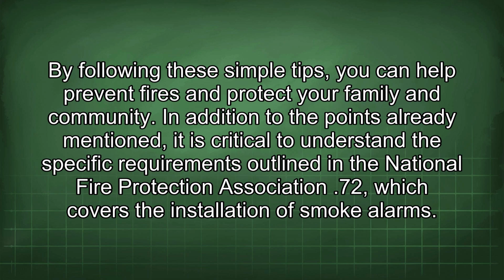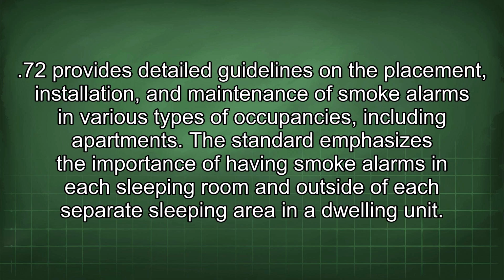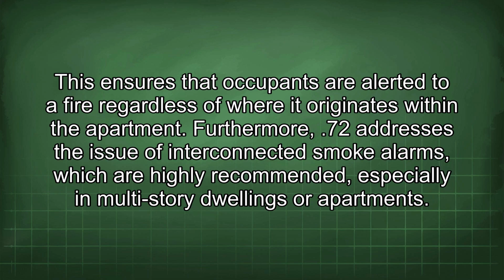In addition to the points already mentioned, it is critical to understand the specific requirements outlined in the National Fire Protection Association 72, which covers the installation of smoke alarms. NFPA 72 provides detailed guidelines on the placement, installation, and maintenance of smoke alarms in various types of occupancies, including apartments. The standard emphasizes the importance of having smoke alarms in each sleeping room and outside of each separate sleeping area in a dwelling unit. This ensures that occupants are alerted to a fire regardless of where it originates within the apartment.